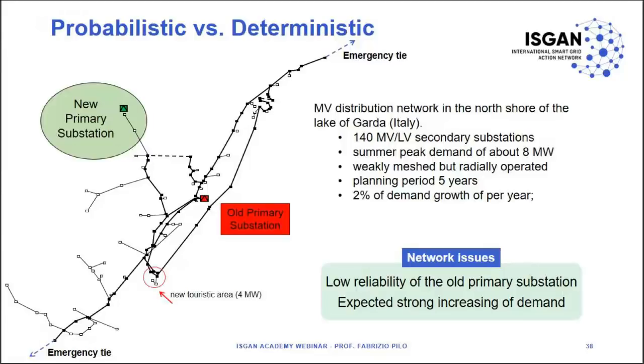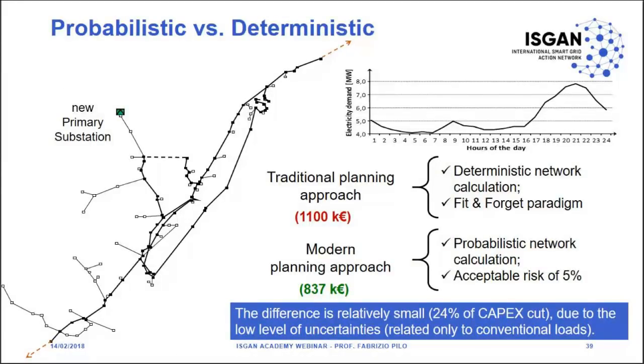The other point is whether we need this new primary substation because a new touristic area is being built that will demand 4 megawatts. We studied this system with both a traditional approach and a modern planning approach based on probabilistic network calculation, with an accepted risk level of 95% probability of not exceeding voltage and thermal capacity limits. In this case, there isn't really a good reason to abandon traditional planning, because we know the load very well.